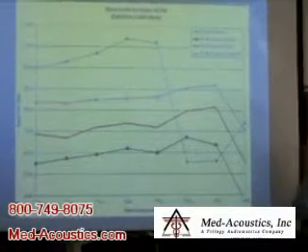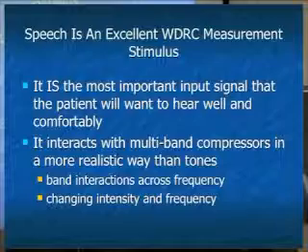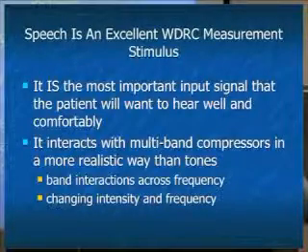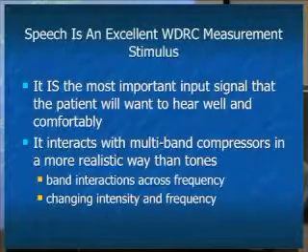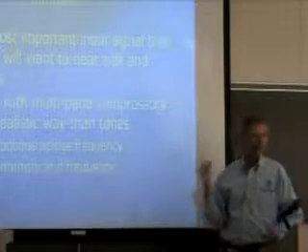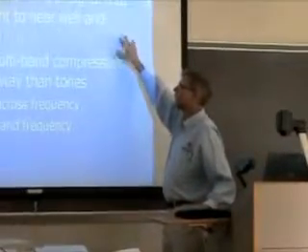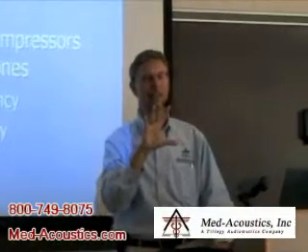Nobody does that anymore, but the reason I showed you these slides is to make the point that the signal you use to fit the hearing aid has to be speech. That's why visible speech mapping is recommended over other methods - speech is the most important input signal the patient will want to hear, hear well, and hear comfortably. Speech is processed differently than other signals because it is much more complex.